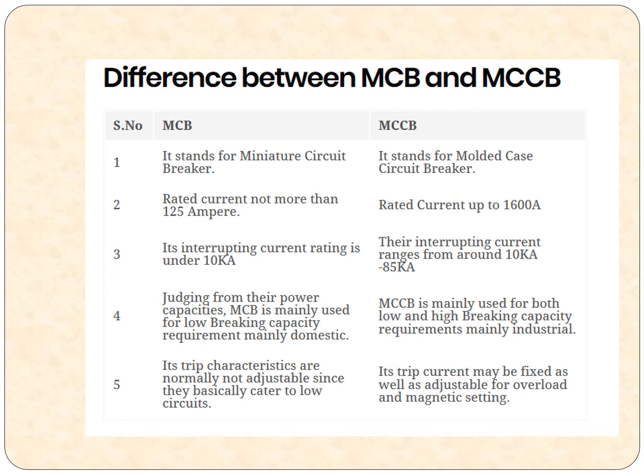So here is the difference between MCB and MCCB. What we mentioned earlier will be displayed here. MCB has a rated current of 125 amps, while MCCB is rated at 1600 amps, and of course the MCB interrupting current is 10 kilo amps. MCCB of course has a higher handling capacity, up to 85 kilo amps.